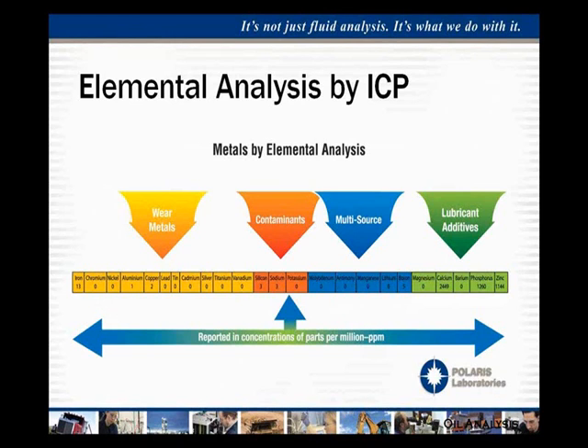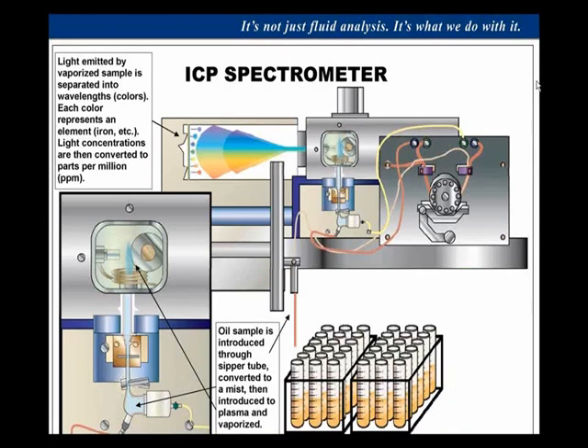We have our multi-sourced elements: molybdenum, antimony, manganese, lithium, and boron. And then we have our additive elements, which are magnesium, calcium, barium, phosphorus, and zinc. We look for combinations of these types of elements to determine what exactly is going on. What basically happens is the oil sample is introduced through a sipper tube, then irradiated and vaporized. We measure the wavelengths of light emitted through this vaporization, and from the light concentration we determine specifically how much of that element is present within the fluid.